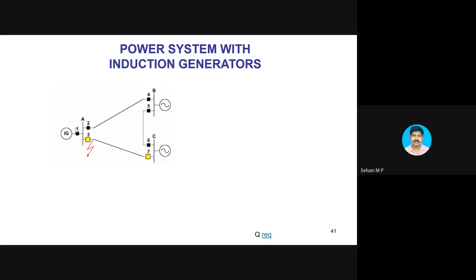Then another case study which I would like to show is a case with induction machine and synchronous machines put together. This is the actual grid scenario, right? Here I'm considering only squirrel cage machines. I'm not considering a doubly fed induction machine or permanent magnet alternator based wind turbines. That is different. With those also you need a STATCOM operation, which can be obtained from the power converter available with the machine itself. Doubly fed induction machines and permanent magnet alternators have power converters. That power converter can be put partially in STATCOM mode and you can get the reactive power support. So here I am not talking about such kind of machine. It is only based on squirrel cage induction machine.